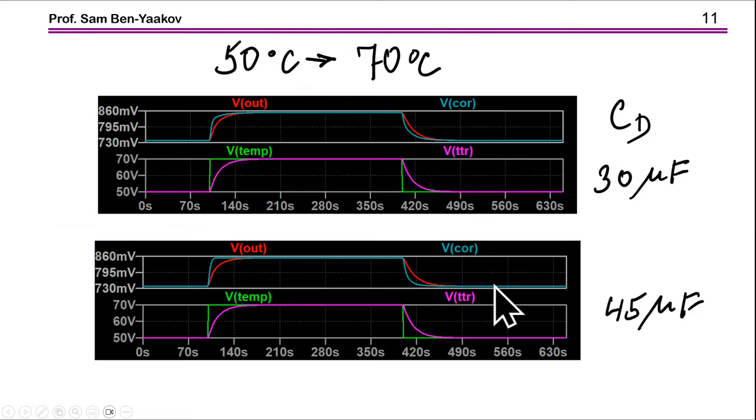Now, with the same 30 microfarad, I'm exposing the system to 50 to 70 degree. Again, it's not very good. And to correct it, I have to put a 45 microfarad capacitor, which brings it to a very nice response.